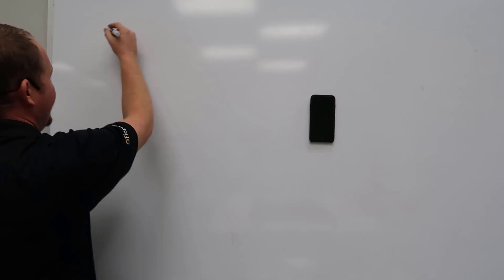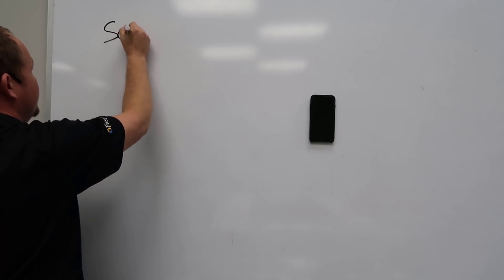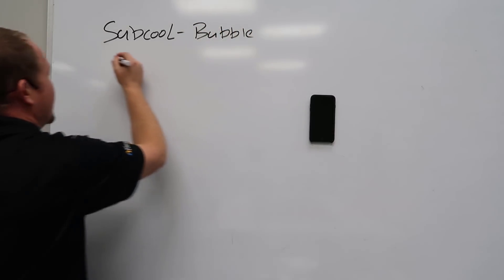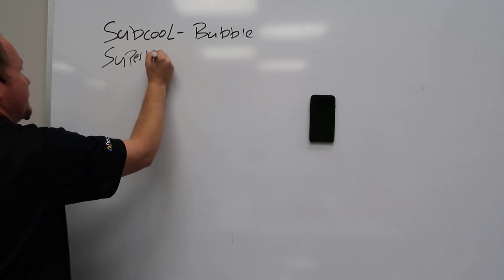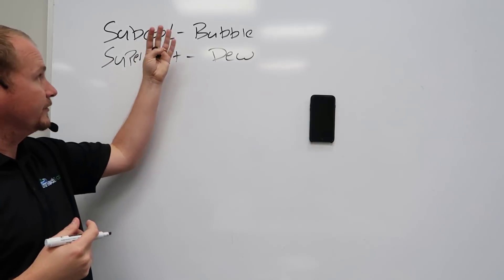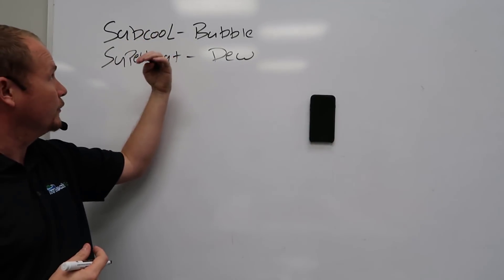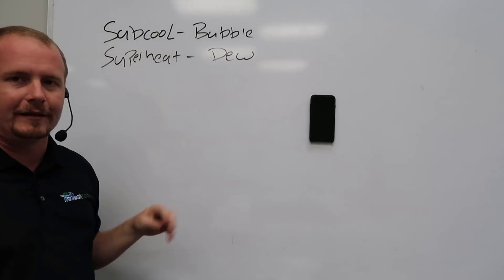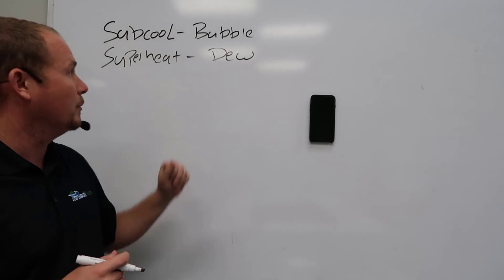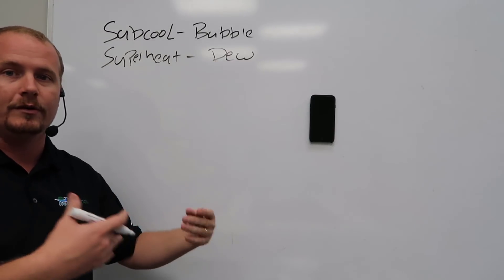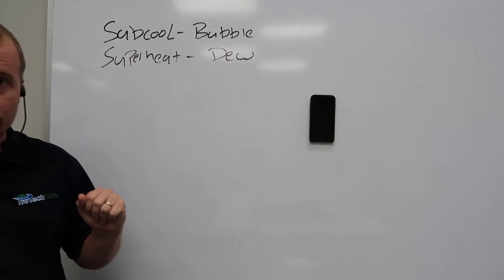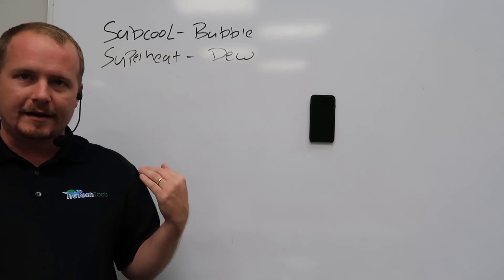This is what most technicians know: for subcooling, we use bubble point, and for superheat, we use dew point. The way I remember it is that when we think of subcool, we know subcooling is a subcooled liquid, and bubbles can appear in liquid. You don't see bubbles in a vapor, you see bubbles in a liquid. So subcooling is where we use bubble point. Superheat is dew point. Where do you see dew? You don't see dew in a liquid, you see dew in a vapor. You see dew in the air. Dew comes out of the air and onto the grass or whatever. So superheat is dew point.